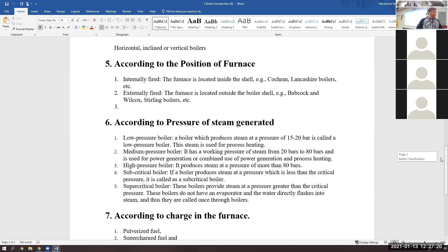Supercritical boilers are interesting because they don't use an evaporator — they go to such high pressure the water flashes directly to steam. This is a little less common because the evaporator allows you to operate at lower pressures. There's a lot of energy going into pressurizing things, and a lot of maintenance issues when things are under high pressure, because now you have downtime as you wait for it to depressurize so you can take things out and work on them. So the efficiency you gain jumping to this versus using an evaporator — you just don't see those maintenance issues that often comparatively.